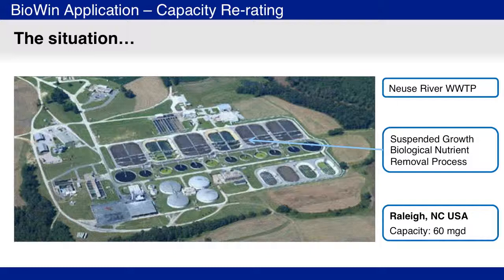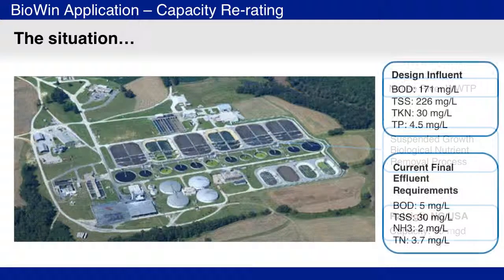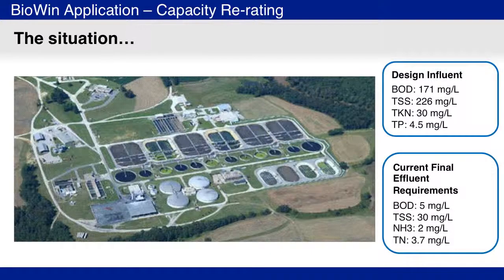This plant is an advanced nutrient removal process with anoxic zones and methanol addition for nitrogen removal, and alum addition for phosphorus removal. The plant also uses 12 denitrifying sand filters. The influent is typical for North American municipal wastewater. The design average daily flow rate is 60 million gallons per day. The plant has consistently met its effluent requirements, which include BOD, total nitrogen, and total phosphorus limits. It has been recognized by the US Environmental Protection Agency for both outstanding permit compliance and its biosolids reuse program.